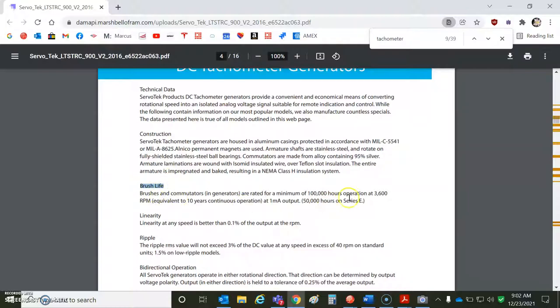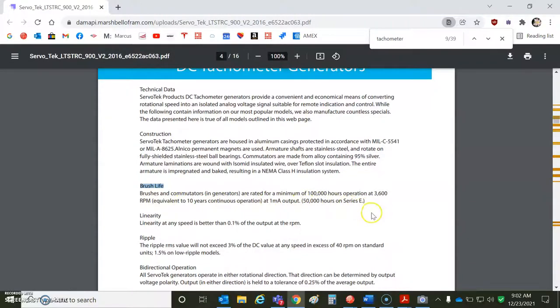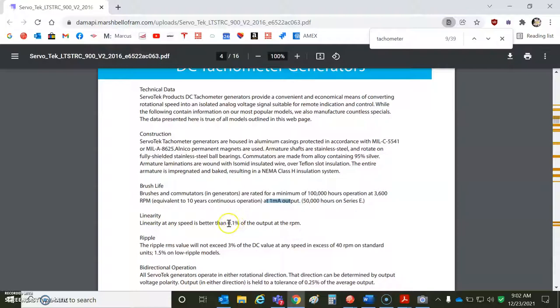Brush life. So your brushes will wear out 100,000 hours at 3,600 RPM, equivalent of 10 years of operation at about one milliamp. So when you generate voltage, you're going to have some current flowing through. So current's probably less than one milliamp at the analog input. Linearity of a tach is good, 0.1% of the RPM.